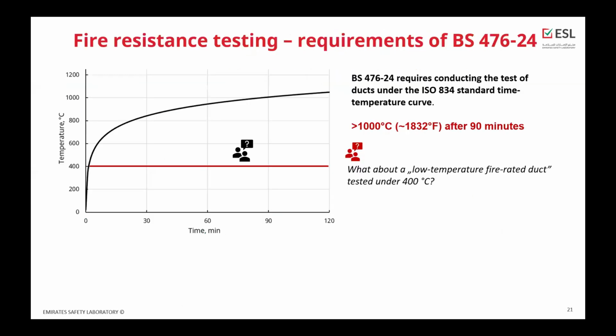So what are the requirements for the BS 476 part 24? First of all, let's talk about the conditions inside the furnace. The BS standard is referring to ISO 834 as a standard time temperature curve inside the furnace, which after 90 minutes is reaching 1000 degrees or above.